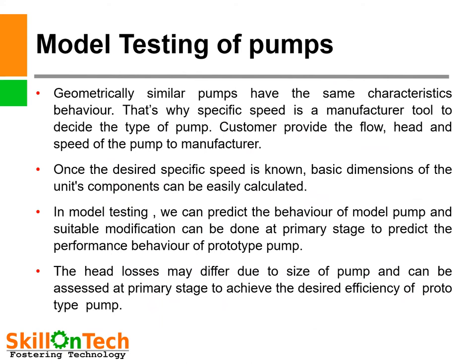This specific speed is also used for model testing of pumps. Geometrically similar pumps have the same characteristic behavior, which is why specific speed is a manufacturer's tool to decide the type of pump. In model testing, we can predict the behavior of a model pump, and suitable modifications can be made at the primary stage to predict the performance of the prototype pump. Head losses due to pump size can also be assessed at the primary stage to achieve the desired efficiency of the prototype.